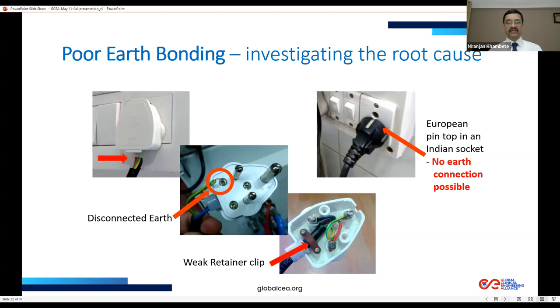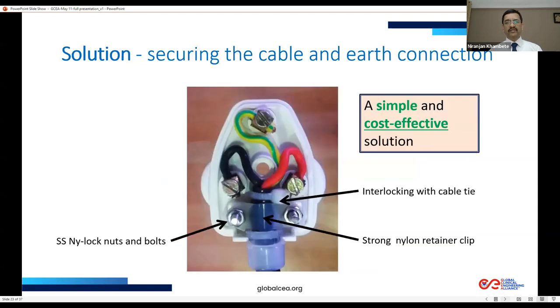In our experience, we attempted to find a solution and then propagate it. We developed a strong nylon retainer clip using a basic material used for making cable ties. We changed the securing arrangement using special nylon nuts and bolts so they don't come out due to vibration, and added an interlocking cable tie to make sure the cable doesn't slip despite all the tightening.